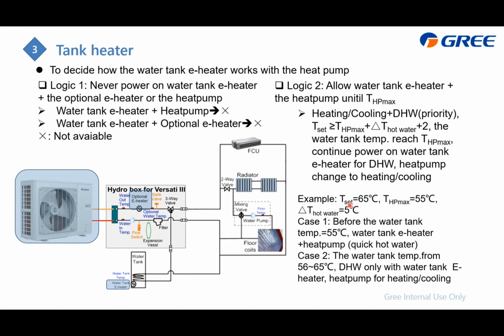So for example, if the T set at the water tank is 65 degree and T heat pump max is 55, this can be edited, and this one is 5 degree. So case 1 is before the water tank temperature becomes 55 degree: the water tank heater plus the heat pump, which will provide quick hot water, so we can make the DHW heat up as soon as possible. And case 2 is the water tank detected temperature from 56 to 65 degree. At that time, the DHW is already heated up by the water tank heater, and the heat pump will change to the heating or cooling.